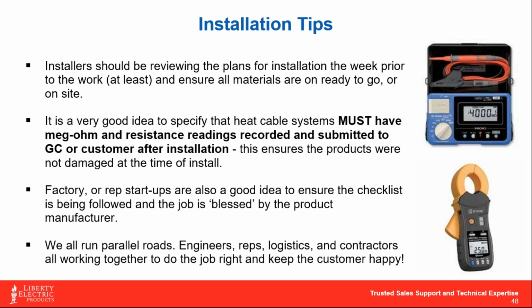Many times it's not the actual installing contractor that damages the cable—it might be one of the other crews on site. The concrete guys, I like them, but they can be animals. I don't mean that disrespectfully, but they're used to plunging shovels, rakes, and screeds into wet concrete. If they hit one of those cables, there's a real good chance they could damage the jacketing enough to ground fault the system. You'll find that out the first day you start it up, and that breaker keeps tripping.